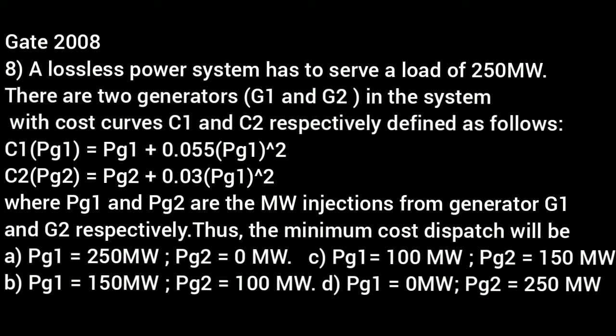That is dC1 divided by dPg1 is equal to 1 plus 2 into 0.055 Pg1. Let it be equation 1. And dC2 divided by dPg2 is equal to 1 plus 2 into 0.03 into Pg2. Let it be equation 2. For economic operation, dC1 divided by dPg1 is equal to dC2 divided by dPg2. So, that is 0.11 Pg1 is equal to 0.06 Pg2.